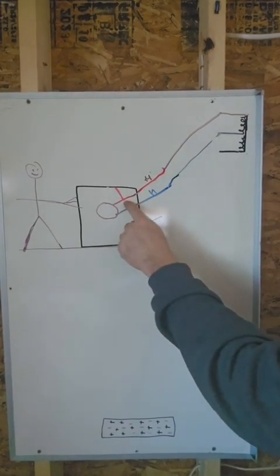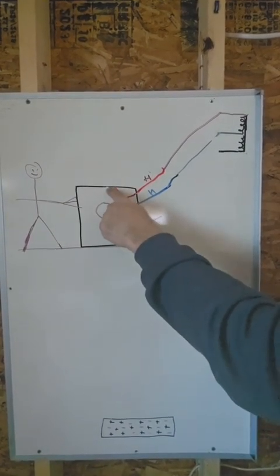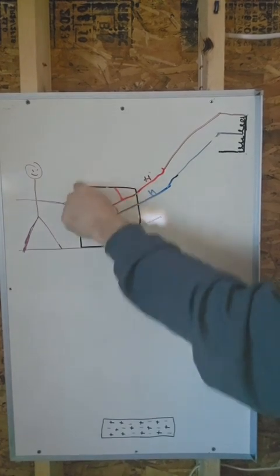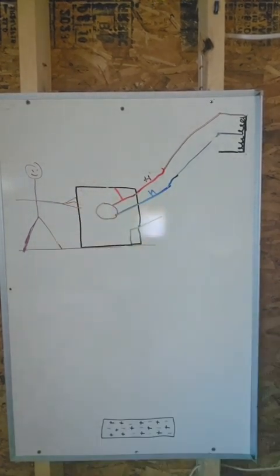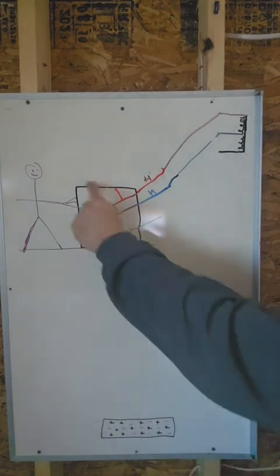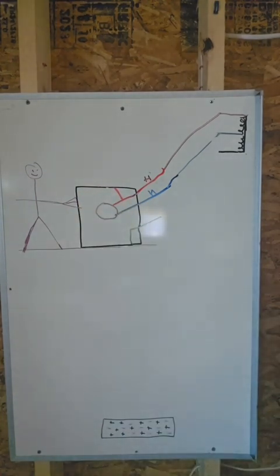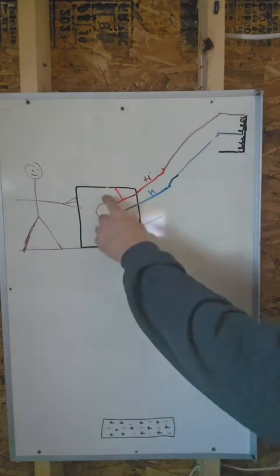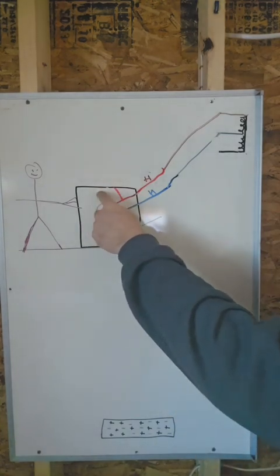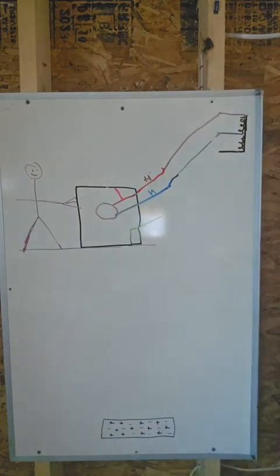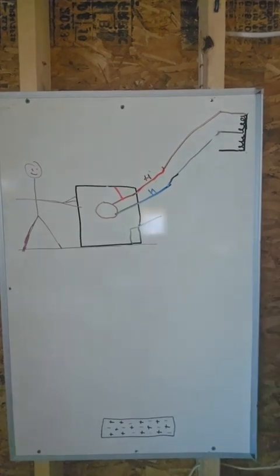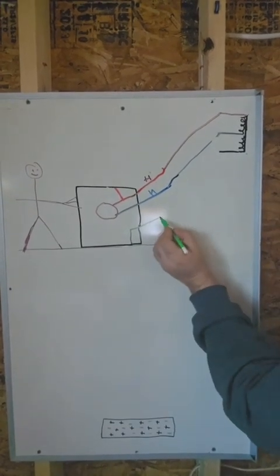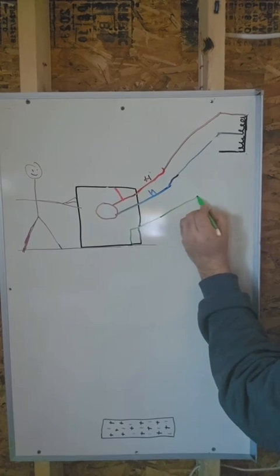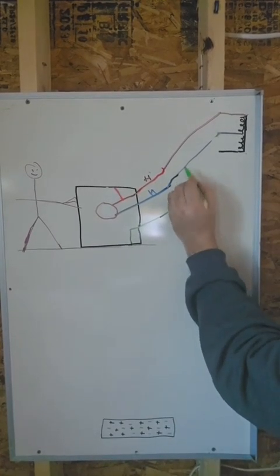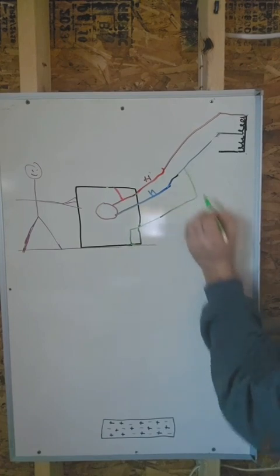But what would happen if this hot wire was chafed or nicked and came in contact with the metal casing of this equipment? The outer metal casing becomes energized, and now anyone touching it becomes energized. So we want a way to keep this outer casing safe to touch. So what we want to do is set it up so that if electricity does touch this, it has a low resistance path straight back to the neutral and pops open the breaker. And it creates an overload situation by touching the casing. And the way we do that is at the meter or the main breaker, the first point of disconnect, we take a wire from the outer casing and connect it to the neutral.